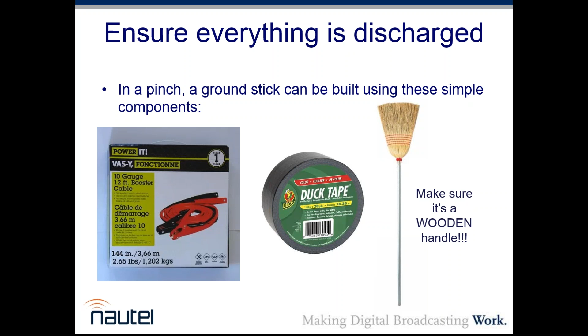You want to be sure you're connected to a ground strap, going to a known connected ground rod, and preferably a brazed one that's not going to oxidize and make a bad connection on you. Yep. And coming back to my friend that came across the 5,000 volts, once you've gone through with your ground stick and discharged everything, grab either this AC alert, or you can grab just a safety voltmeter. The safety voltmeters are cool because they allow you to clamp on one side, like the ground, and just use the meter with the probe clipped into it, so you've got some separation.